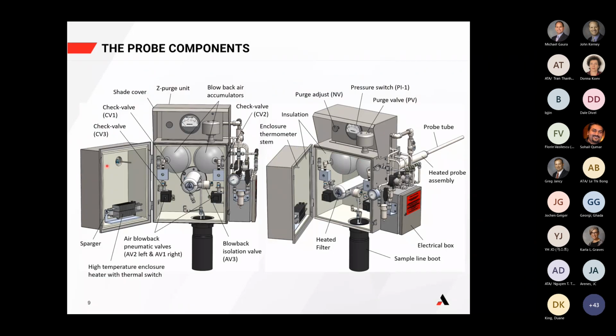Here's kind of an exploded diagram, bringing them out individually. The heart of it is really the temperature controlled zone. So the heated probe tube assembly, the heated filter, and then the heated box itself. These do 90% of the lifting for the SSP probe, and the other 10% of the lifting is done by the blowback in terms of preventing probe tube fouling. All the wetted components are available in 316. We also offer Hastelloy C276, and I believe there's some high temperature alloy development in the works as well.